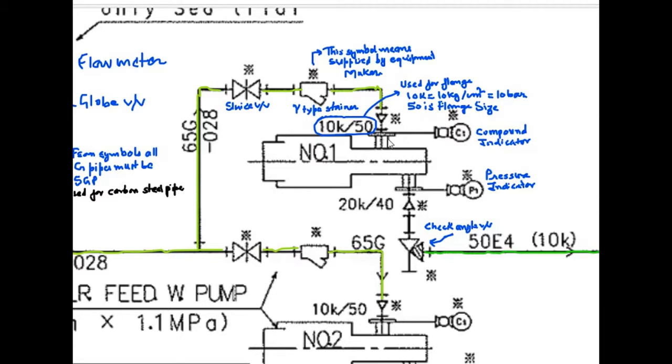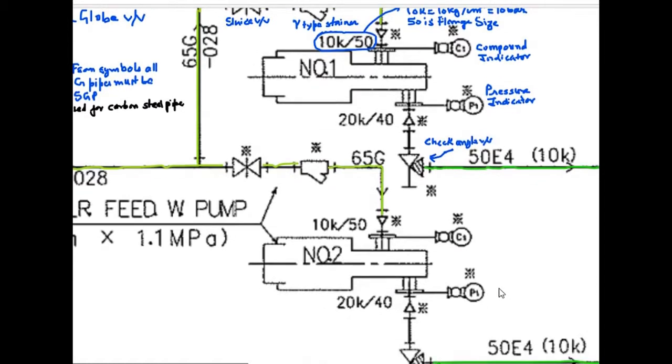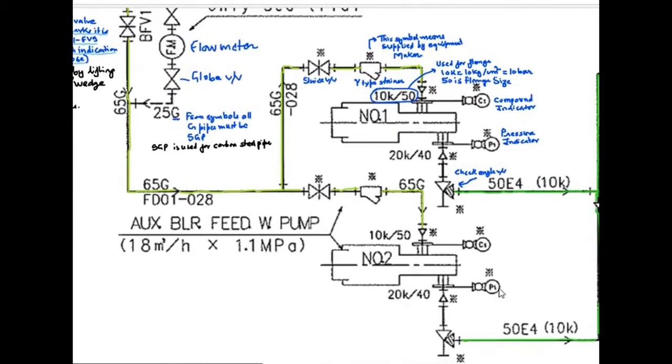On the suction side, we have a compound indicator. CI is the compound indicator symbol. This is number one feed water pump. And on the discharge side, we have pressure indicator. And on the discharge side, we have a check angle valve. It is like a non-return valve which does not allow the fluid to go from one direction to other. Similarly, other pump, the same symbols are there. Both the discharge lines are connected.